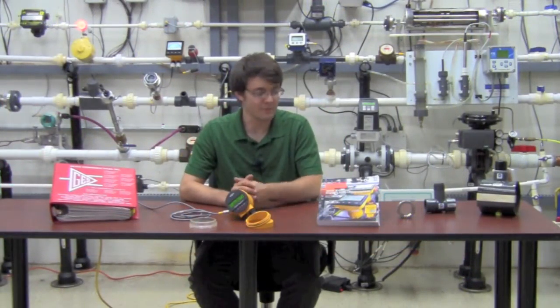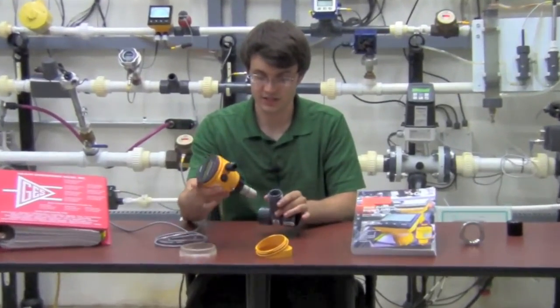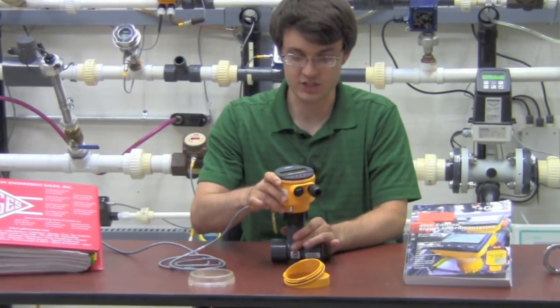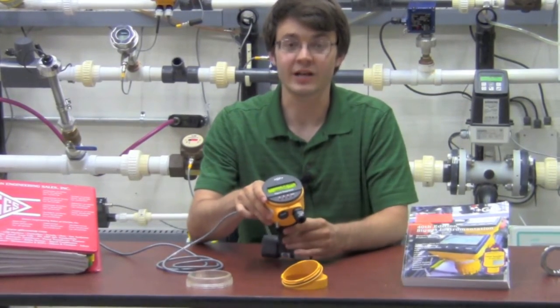Using one of Signet's pipe mounting options like this T, installation is a breeze. Simply insert the meter to the fixed insertion depth per that T, screw down the compression fitting, and we're ready to program.